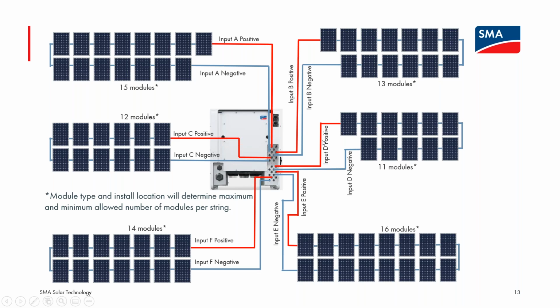And again, just trying to emphasize, make sure everyone's aware that the 6 tracking channels for each unit can be connected with strings of different length, different orientation. They could even be different module type. If you need to clean out the warehouse and you don't have enough of the same type module to connect to the inverter, and no one's going to see that roof and say, why do the modules all look different? It is certainly electrically possible. Again, you have a very wide voltage range for each of the inputs, and the inverter manages each one independently.